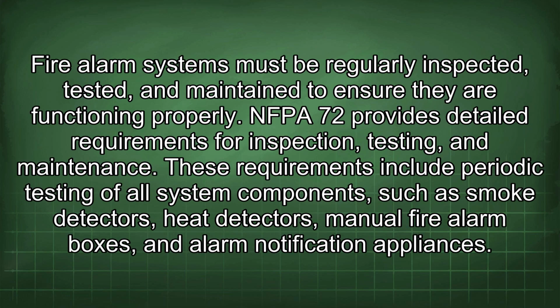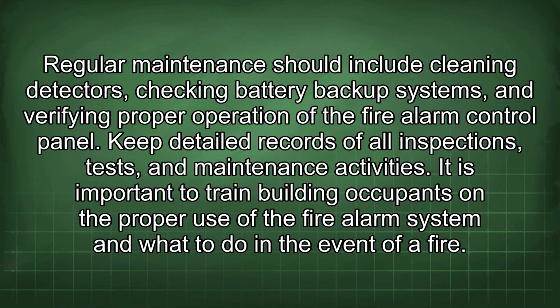Fire alarm systems must be regularly inspected, tested, and maintained to ensure they are functioning properly. NFPA 72 provides detailed requirements for inspection, testing, and maintenance. These requirements include periodic testing of all system components, such as smoke detectors, heat detectors, manual fire alarm boxes, and alarm notification appliances. Regular maintenance should include cleaning detectors, checking battery backup systems, and verifying proper operation of the fire alarm control panel. Keep detailed records of all inspections, tests, and maintenance activities.